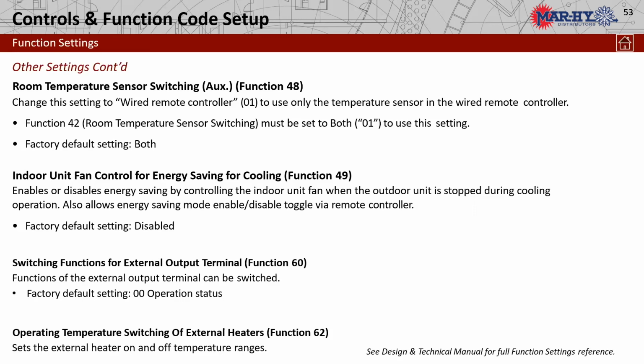On our startup guide, we'll have this all listed so that inevitably when you get done doing all of the settings, our temperature sensing will be done at the thermostat. So indoor unit fan control, function 49. This is the same function as the one we talked about in heating, where we slow the fan down during the thermal off mode. We would enable this function, and it will take it to low in the thermal off mode in cooling. That's function 49.